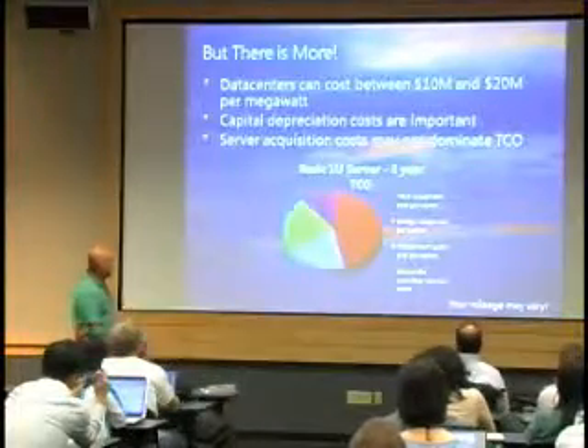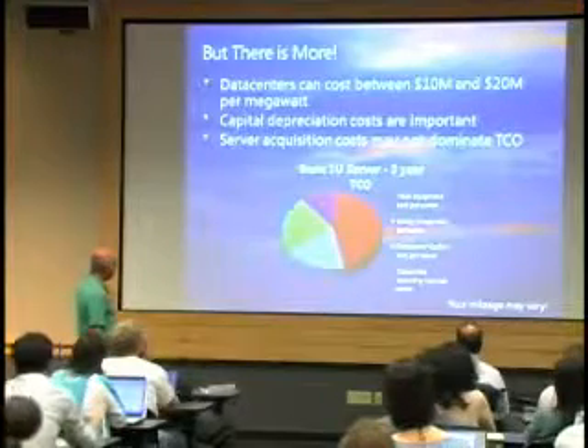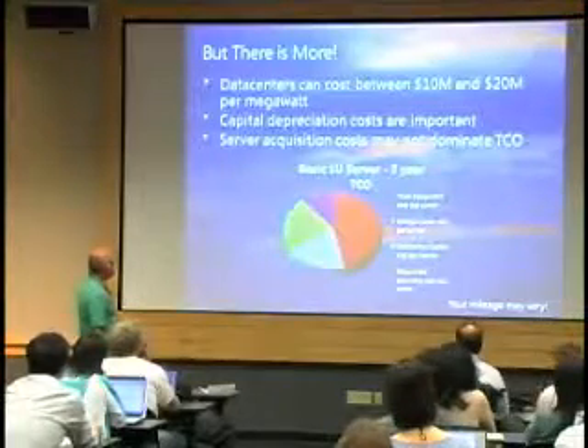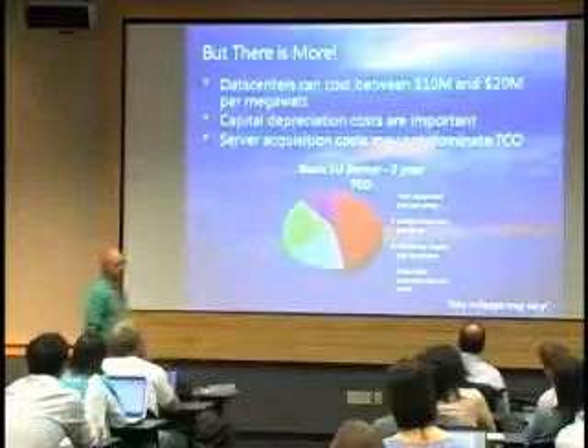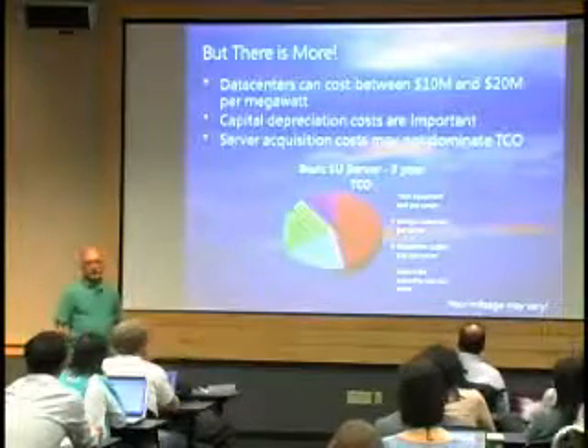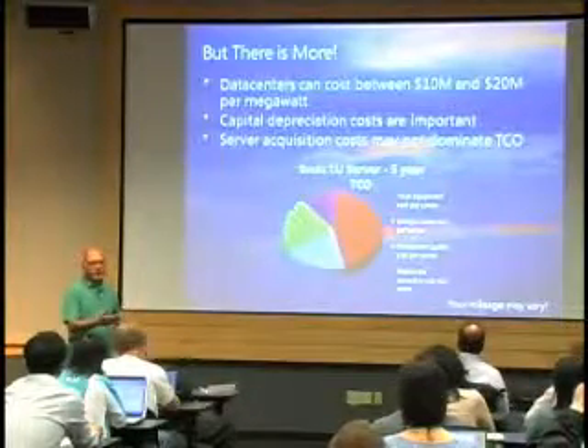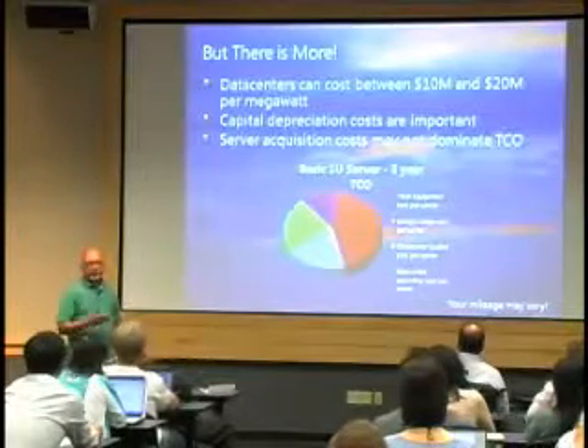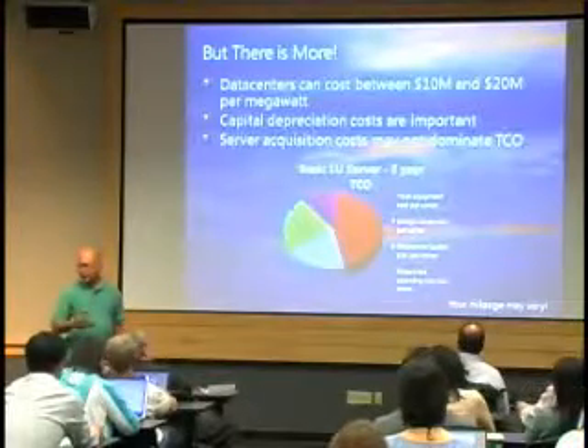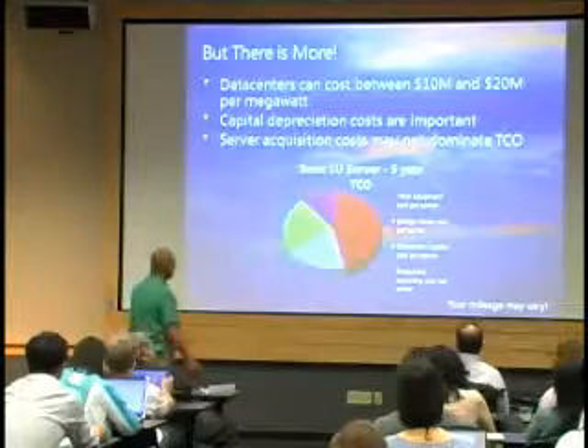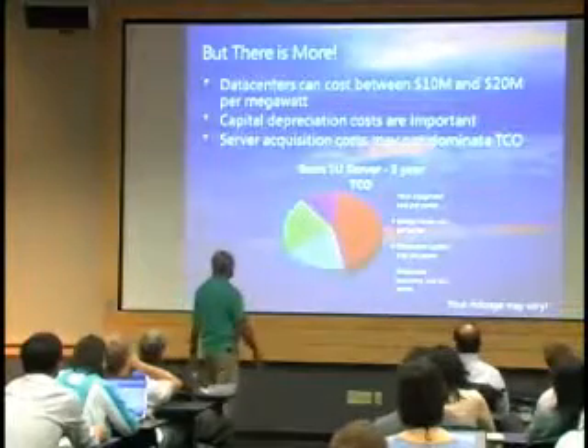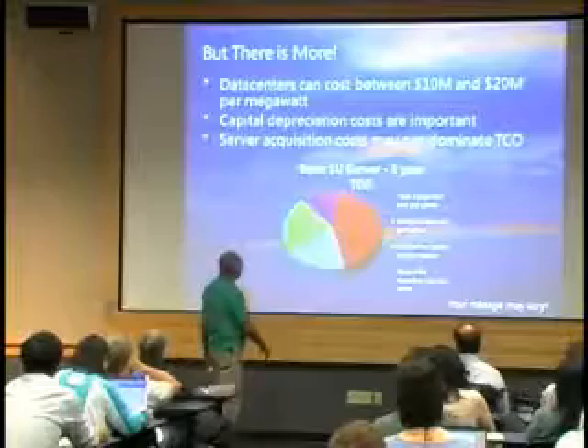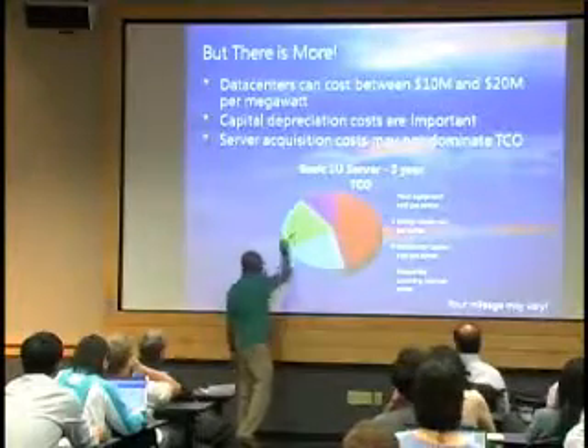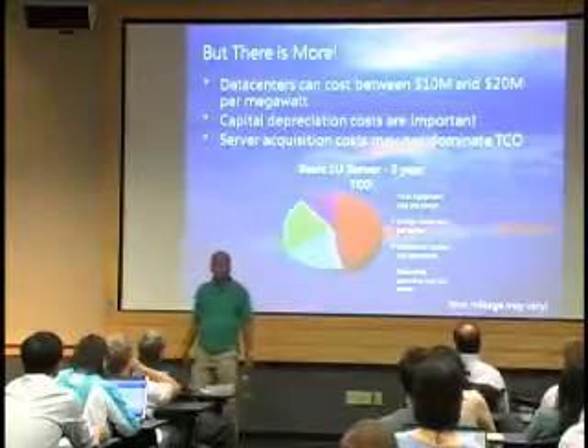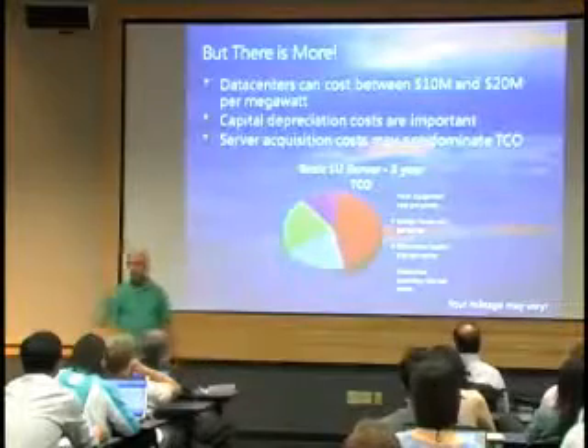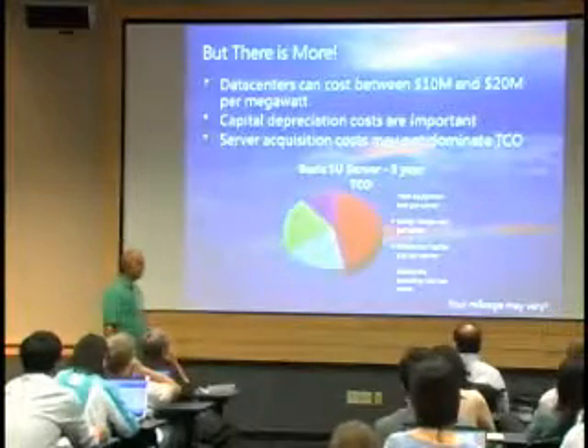I did this with a server that was about 300 watts or somewhere in that range. So if you're building, let's say, a 20 megawatt data center, you need to allocate the capital cost, the depreciation on that capital investment, in proportion to the energy being consumed by that particular server. When you do that, what you end up with is this green piece of the pie, which is about a quarter of the cost - that's the depreciation allocated to that server.